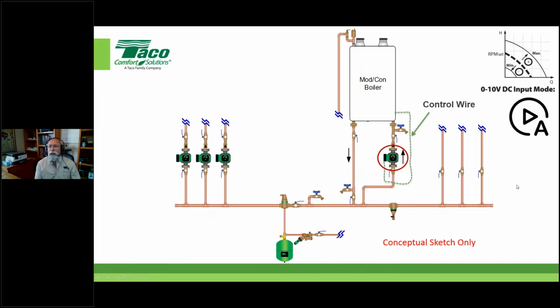But one thing that I mentioned on one of my bullets is the ability for the boiler manufacturer now to have control of the circulator. So what I'm saying is a pump manufacturer like Taco now gives the keys to the boiler manufacturer. Here's the keys, you run me however you see fit. And we're doing that, typically in North America, with a 0 to 10 volt DC signal down to the circulator. This is not just powering the circulator, it's saying, look, I'm going to power the circulator and I'm going to control its variable speed based on input that I'm receiving from something within the boiler manufacturer's equipment, right?